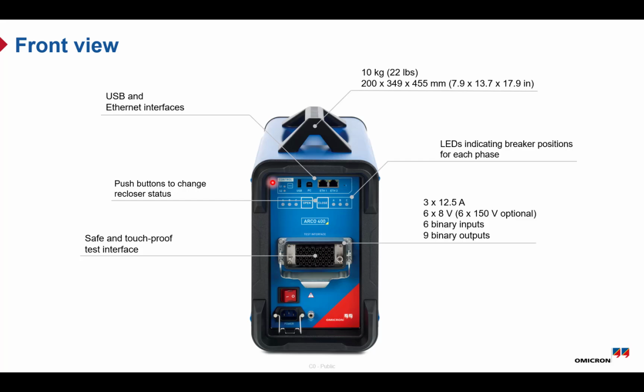On the front panel, you also have LED indicators that show the breaker status for each phase, whether it's open or closed. This gives you a quick visual confirmation during testing. There is also a control button that allows you to simulate breaker operations directly from the device, as open and close commands.